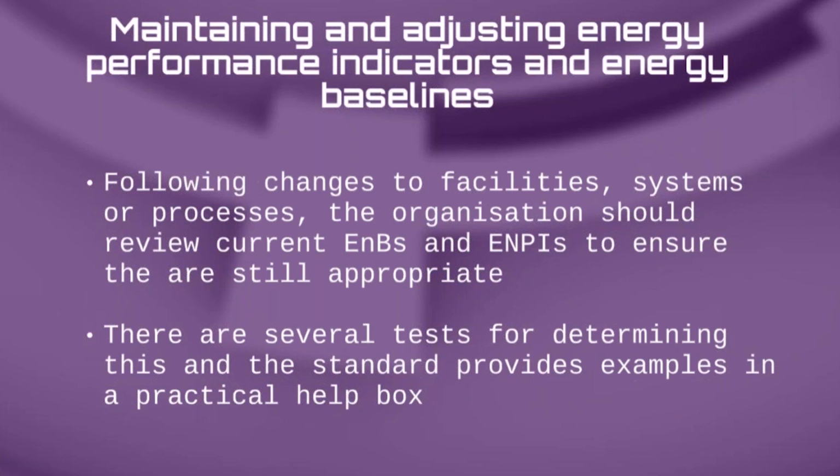So you could have changed the fuel you're using. In manufacturing, you might have changed materials. You might have gone from manufacturing something with aluminium frames and replaced it with plastic frames. Could have an impact, and you need to reset your baselines and start again from that point. Or it could be a complete change of use of the building, which would justify resetting and starting again. As I said very early on in the presentation, baselines are not fixed forever. If things change, you do need to have a process for reviewing that and effectively resetting the baselines and starting again.